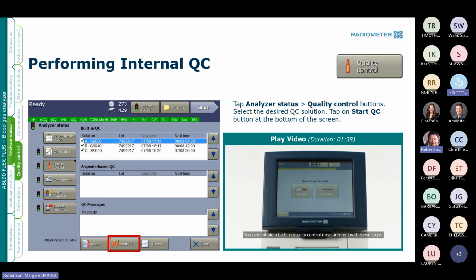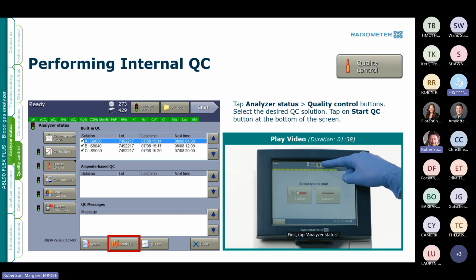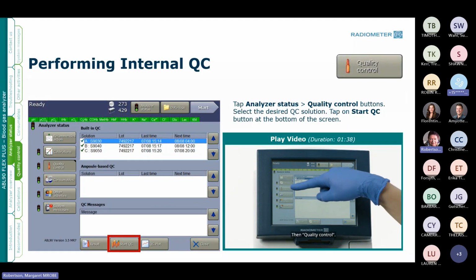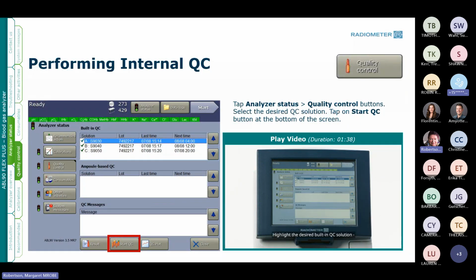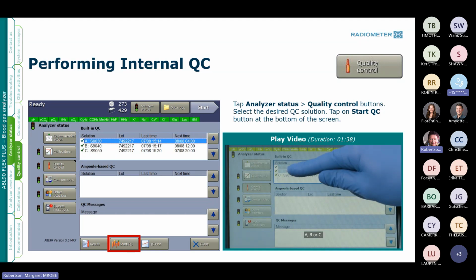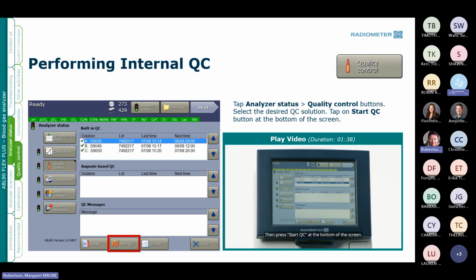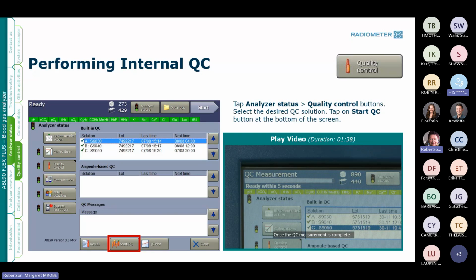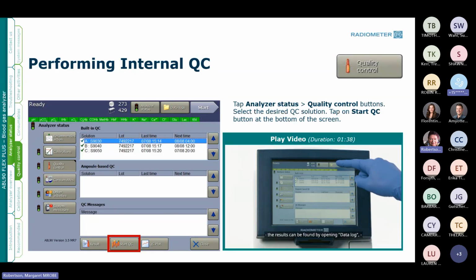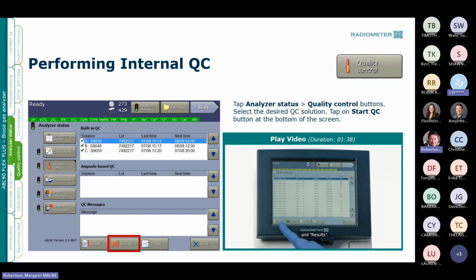You can initiate a built-in quality control measurement with these steps. First, tap Analyzer Status, then Quality Control. Highlight the desired built-in QC solution, A, B, or C. Then press Start QC at the bottom of the screen. This will start the QC measurement. You will be unable to analyze other samples while the analyzer measures the QC. Once the QC measurement is complete, the results can be found by opening Data Log, Quality Control Log, and Results.